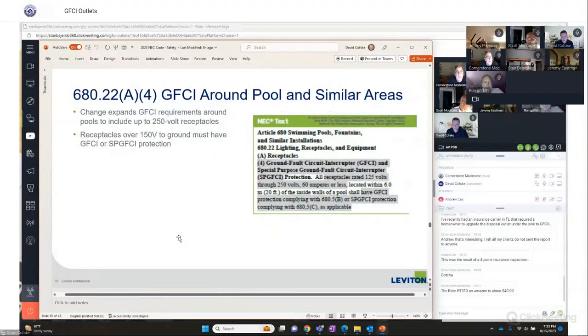And then this talks about, under this code article, 250 volt receptacles. So sometimes you'll have heaters and other devices that are 240 volt powered, and now those need to be GFCI protected.